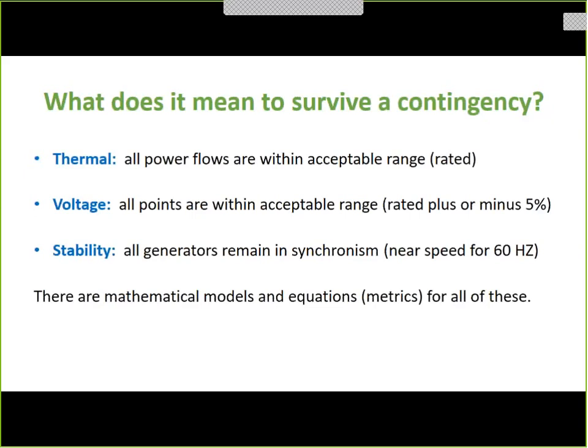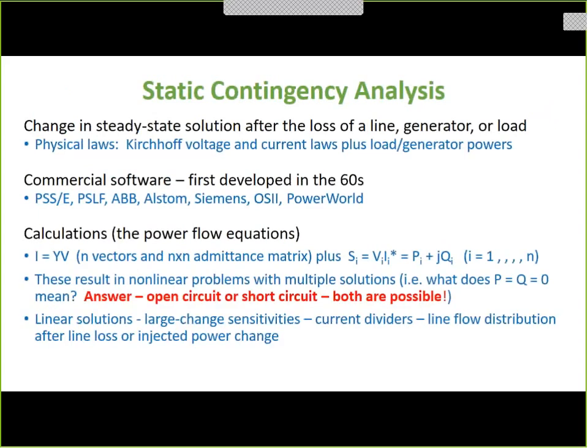Stability. All generators have to remain in synchronism. If we're talking about a synchronized grid, that means the speeds are near the equivalent for 60 hertz. We use mathematical models for all three of these things. It comes in two forms, static or dynamic. Static contingency analysis is really just looking at steady state solutions. If you outage a line, where did the current go and what happened? That's steady state. So there's no disturbance really other than that. There's no fault, there's no short circuit, there's nothing that's causing things to change.